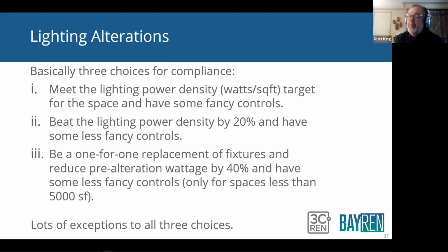When what they wanted to do was really improve the lighting efficiency of the system, the new code handles this much better, and that's this option number three. And what it says is be a one-for-one replacement of fixtures and reduce the pre-alteration wattage by 40% and some less fancy controls. You still have to have your basic mandatory controls, okay? And this only applies to spaces less than 5,000 square feet.